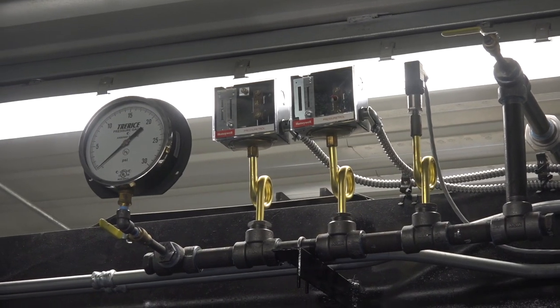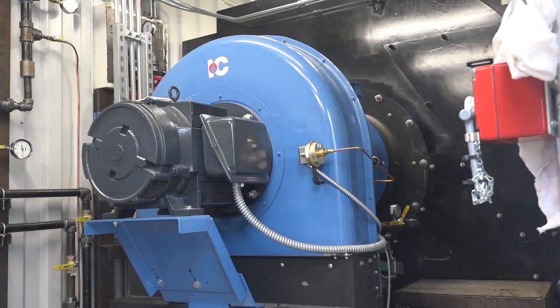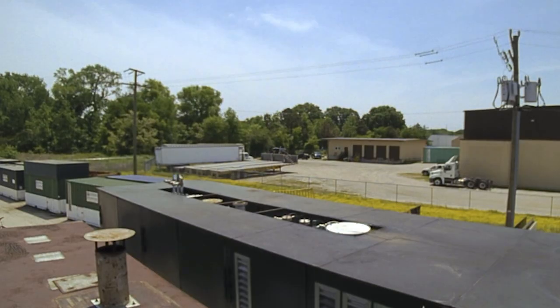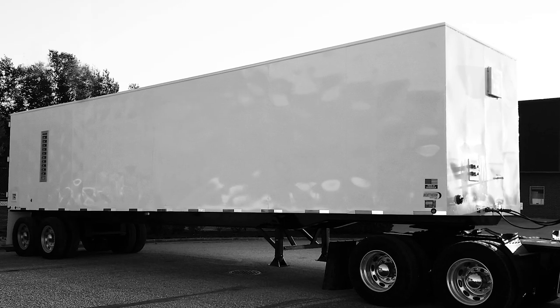As mentioned, they are pre-piped and pre-wired, so field installation usually means attaching the supplied stop and check valve, the steam valve, the stack hat, then connecting to the facility, bringing in the main power, filling the boiler up, and bringing it online. The mobile boiler plant is ideal for planned or unplanned outages, as well as supplemental and primary steam where sites may need the amenities of a complete boiler room all in one package unit.